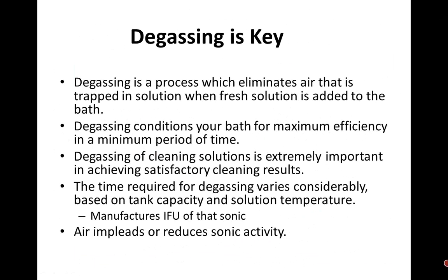Degassing of the cleaning solution is important. It's helping you achieve satisfactory cleaning results. And if you're using no cleaning solution, such as with your eye instruments, you still have to do it. The time required for degassing varies considerably based on the tank's capacity and size and the solution temperature. And where do you get that information from? The manufacturer of the sonic will say that before you begin, you degas X amount of minutes. Again, air impedes or reduces sonic activity.